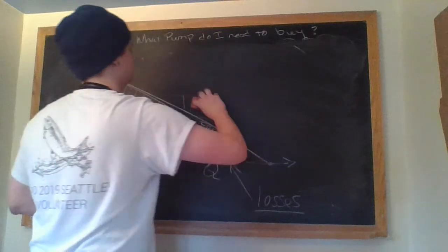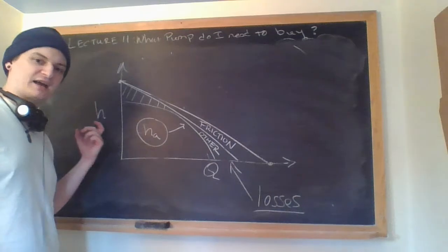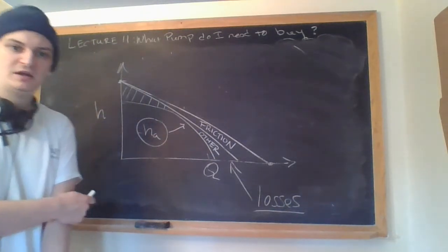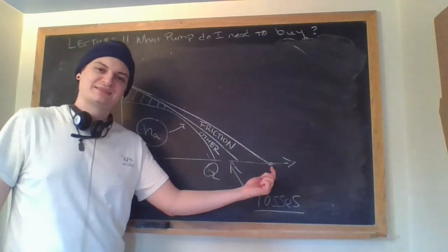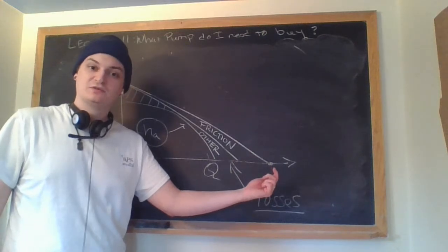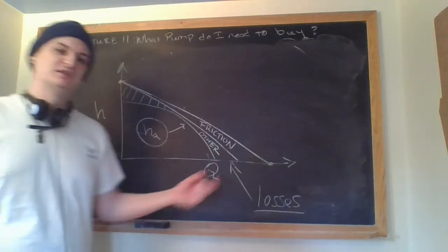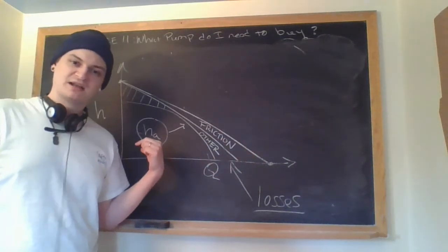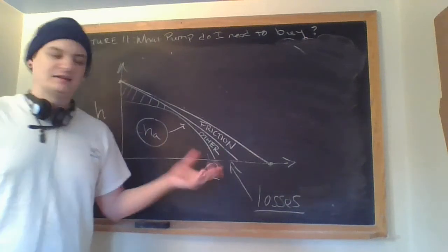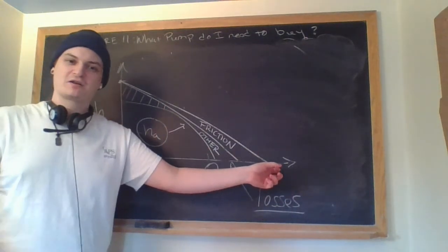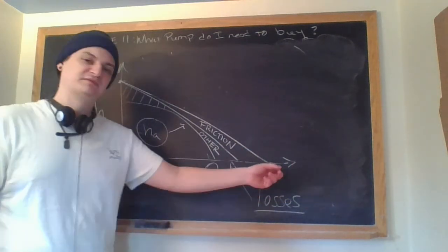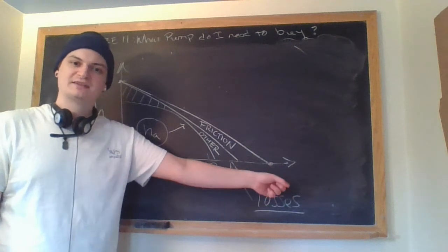And that is your pump performance curve, and so much can come from this curve, based on relating the flow rate of your pump to the actual head rise it can perform for you. So there is the idea that there is a maximum flow rate a pump can do, and at that point you don't get any head rise. Conceptually that's initially hard to grasp, but I want you to think about it based on all the equations we've done and how to get to this expression. Why should that be the case?